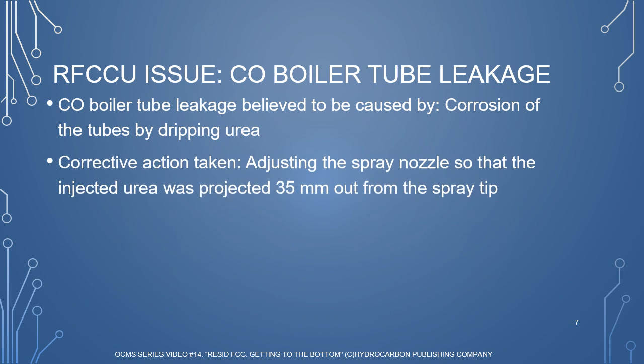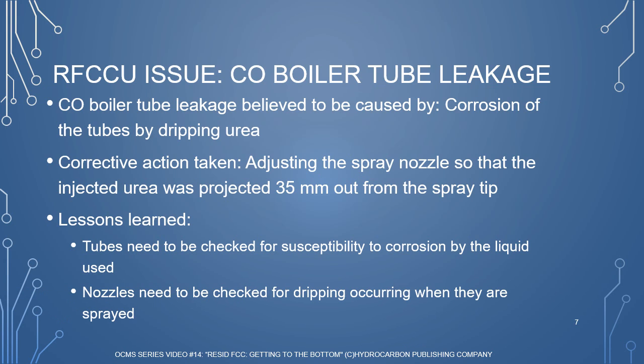The refiner attributed leakage of the carbon monoxide boiler tube to corrosion from dripping urea. The corrective action for this was adjusting the spray nozzle so that injected urea was projected 35 mm out from the spray tip. The lessons learned from this were that tubes need to be checked for susceptibility to corrosion by the liquid used and that nozzles need to be checked for dripping occurring when they are sprayed.